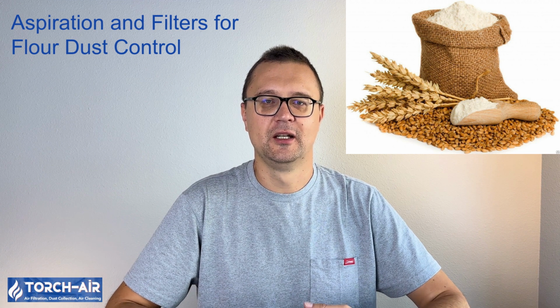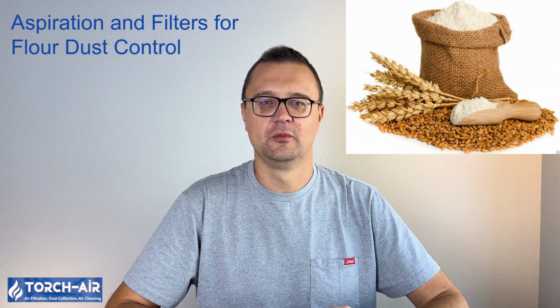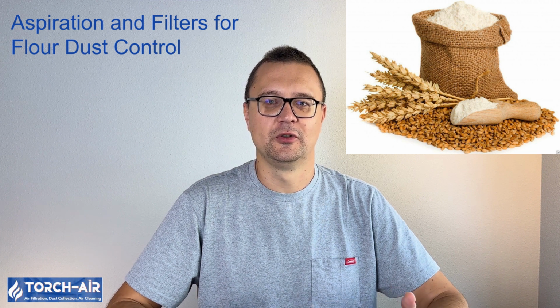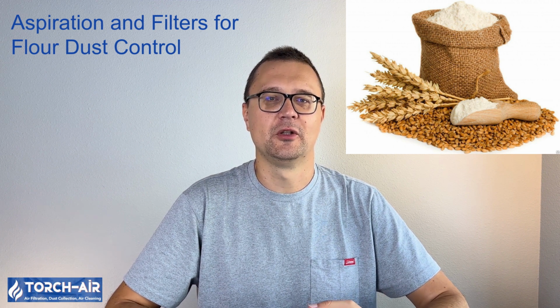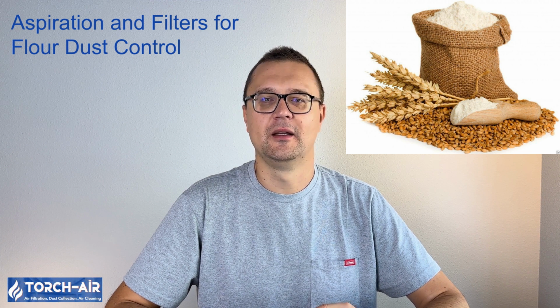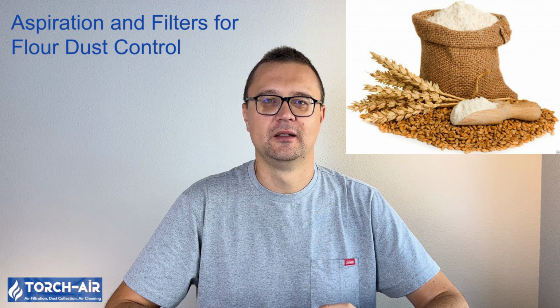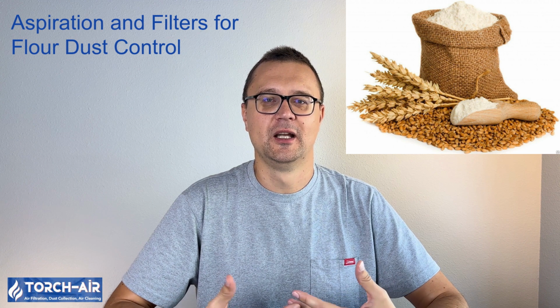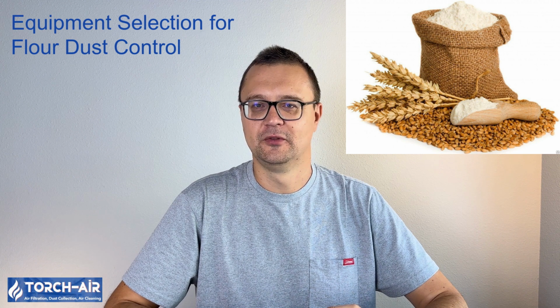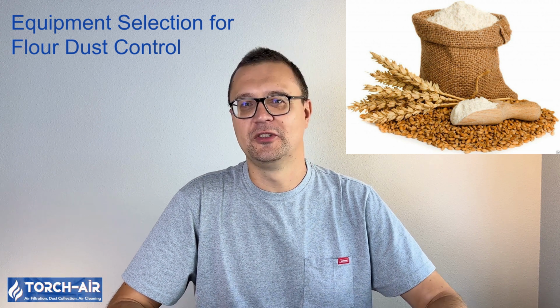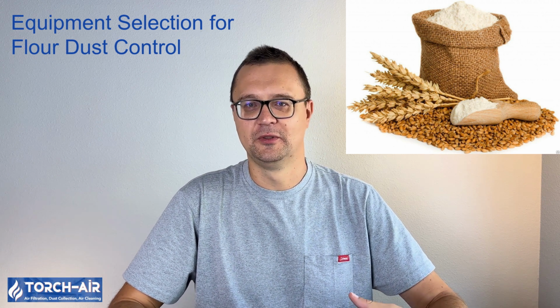Cyclone dust collectors. Cyclones separate dust from air using centrifugal force. While not as efficient at capturing very fine particles, they are good for pre-filtering large volumes of air and reducing the load on secondary filters like baghouses or cartridge filters. HEPA filters, high efficiency particulate air. HEPA filters can capture 99.97% of particles down to 0.3 microns, making them ideal for facilities with stringent air quality requirements.